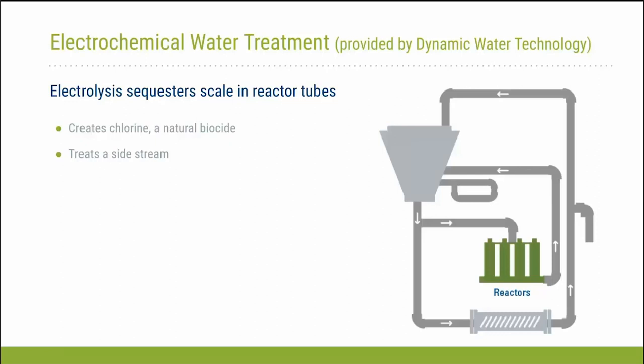This is just a small graphic that shows what I was discussing. That reactor skid, in essence, is taking a very small slipstream, so it's not a really large skid in comparison. It does have a small pump on the system that pulls the slipstream water through the reactors. The energy usage for the skid is low. It's basically a 110 spa-type pump that could plug into an outlet. Again, it sits right next to the cooling tower, and there is a tap required into the piping of the discharge of the cooling tower, but then it discharges directly back into the cooling tower.